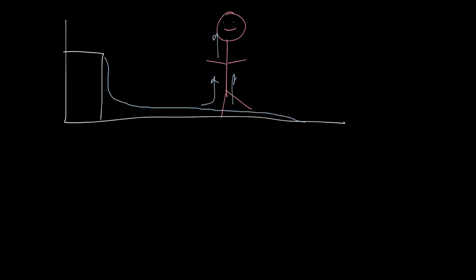So this is a side view of a displacement diffuser along a wall. The cool air leaves the diffuser at a low velocity, moves across the floor, and then rises when it gets to a heat source, like a person. As it rises, it cools the person and provides ventilation air. So even though the airflow leaves the diffuser at a low velocity, it's still above 50 feet per minute at the diffuser face. Per ASHRAE, you don't want to have greater than 50 feet per minute in the occupied zone.